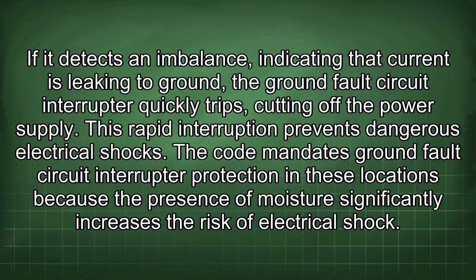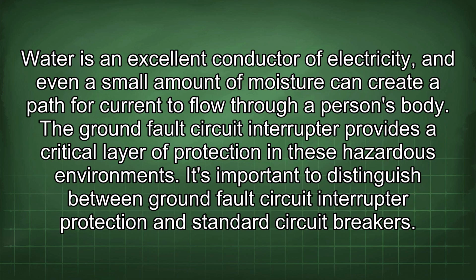The code mandates ground fault circuit interrupter protection in these locations because the presence of moisture significantly increases the risk of electrical shock. Water is an excellent conductor of electricity, and even a small amount of moisture can create a path for current to flow through a person's body. The ground fault circuit interrupter provides a critical layer of protection in these hazardous environments.